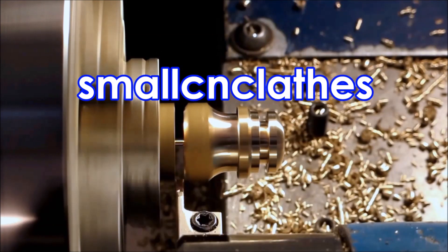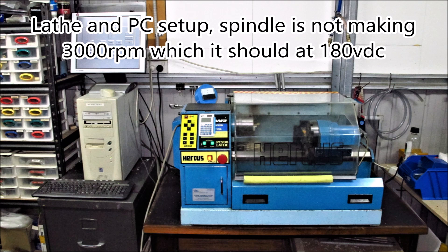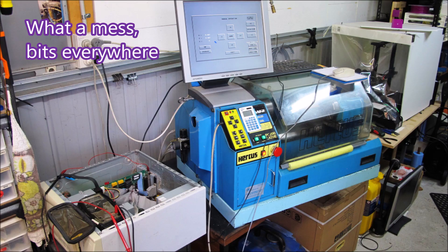I've had trouble getting my lathe to reach its maximum speed of 3000 rpm. In fact, I've readjusted it twice, but this time I've done it again and made a video of it. This is my lathe and the PC which has the software and the electronics to run it. That's a shot of the manual screen and you can see there that it's not reaching its 3000 rpm — it's only getting 2495.